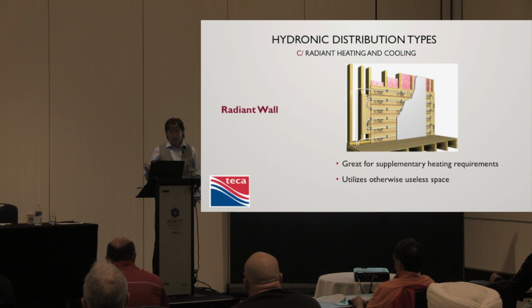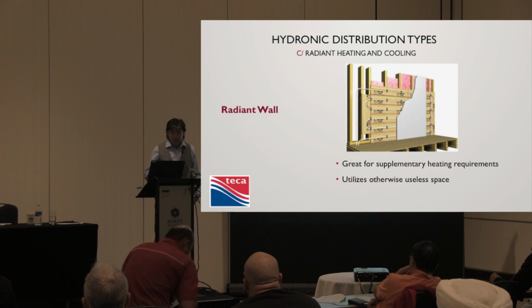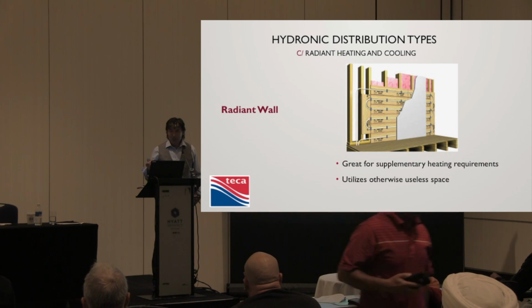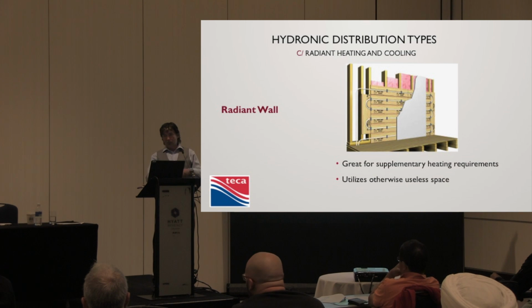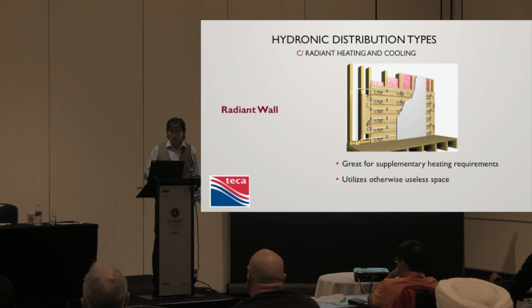Maybe you do that, but really would you? That's quite a negative. And we were talking about this earlier. You go into a restaurant and you've got to pull the door open, and it's just, oh my God, because they're running such a negative with their exhaust fans. That is certainly the case. So that air will come from somewhere. You put 1,000, 800, 600, 1,200 CFM, very common these days. That air's got to come from somewhere. So even though the code doesn't say you have to, maybe you want to think about it anyway, because you're pulling air in through the skin that maybe you didn't want to do. Any other questions? I hope that answers the question.